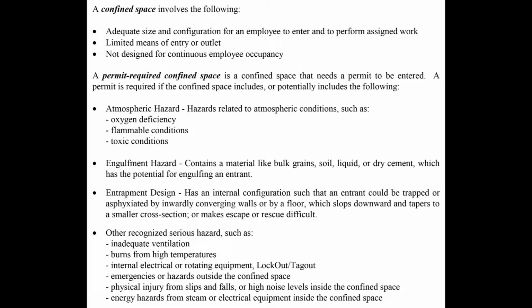A permit is required if the confined space includes or potentially includes the following: atmospheric hazard, hazards related to the atmospheric conditions such as oxygen deficiency, flammable conditions, toxic conditions. Engulfment hazard, contains a material like bulk grains, soil, liquid, or dry cement which has potential for engulfing an entrant. Entrapment design, has an internal configuration such that an entrant could be trapped or asphyxiated by inwardly converging walls or by a floor which slopes downward and tapers to a small cross section or makes escape or rescue difficult.